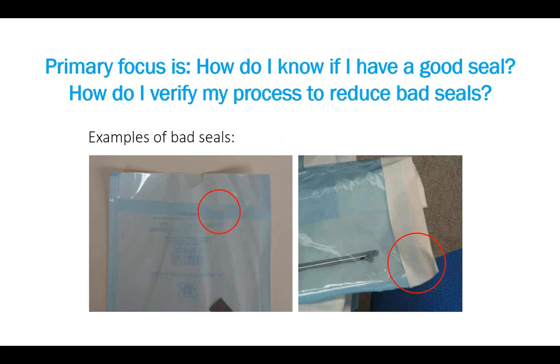How do you verify my process and reduce bad seals? As you can see on the screen, I have circled here what I call rivers. This is a bad heat seal, and a bad seal is a pathway for microorganisms to get through. We also know that in steam sterilization, having air pockets is no good. You can see here in this self seal, look at the opening, and you can trace it all the way back. That is bad seals.